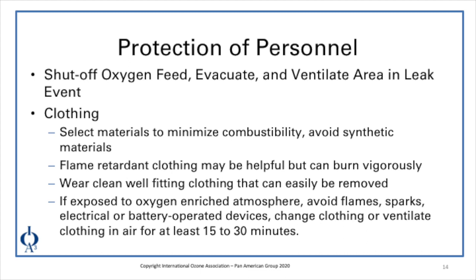Looking at protection of personnel: shut off oxygen feed, evacuate areas, and ventilate areas in the event of a leak before reentering, ensuring the environment is no longer enriched. For clothing selection, select materials to minimize combustibility — avoid synthetic materials when working around liquid or gaseous oxygen. Flame-retardant clothing may be helpful but can still burn vigorously in an oxygen-enriched environment. Wear clean, well-fitting clothes that can easily be removed. If exposed to an oxygen-enriched environment, avoid flames, sparks, and electrical or battery-operated devices. Change your clothes or ventilate your clothing in air for at least 15 to 30 minutes.